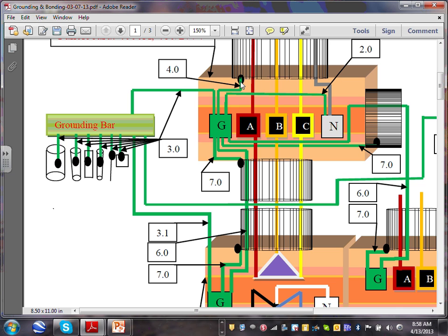There are options where you do not need a wire supply side bonding jumper, because the wiring method qualifies as bonding the conduit to the switchgear. Does that make sense? There are a couple of examples, such as a grounding wedge. I want to remind you, this is special bonding at the service.